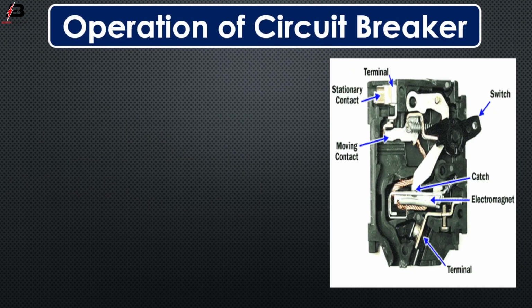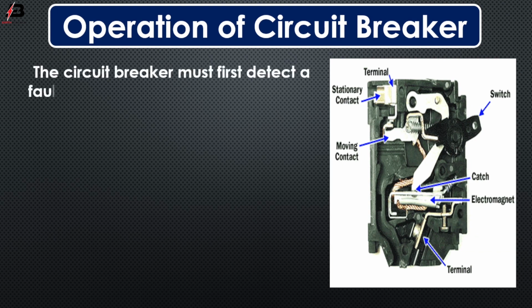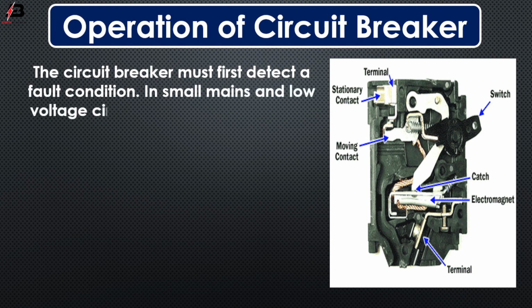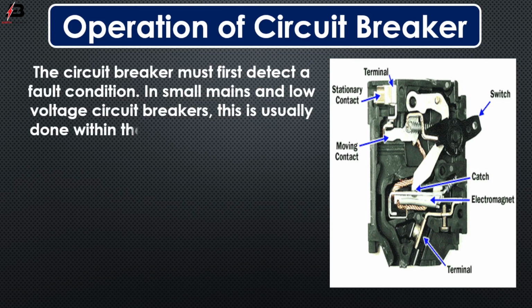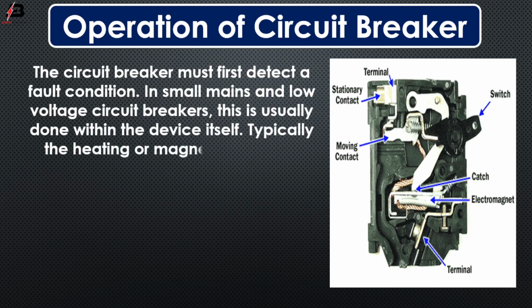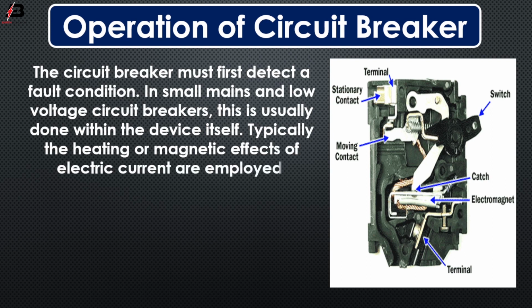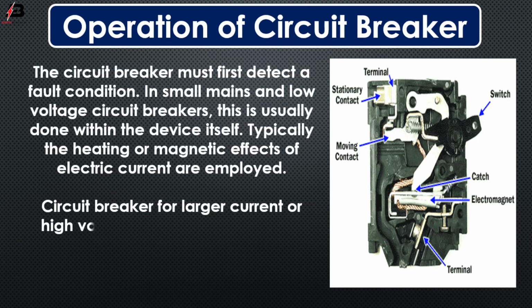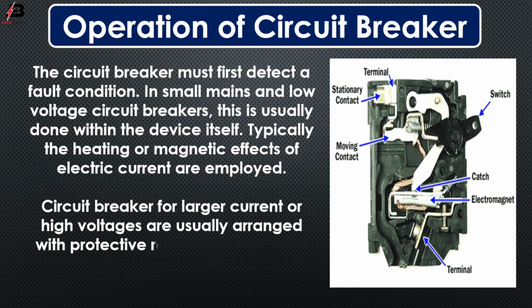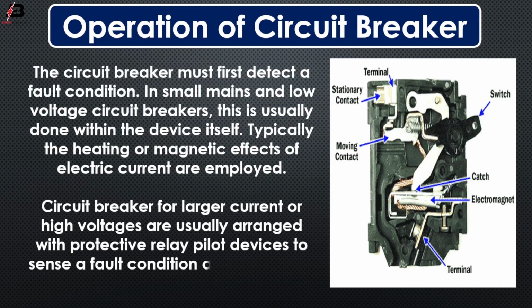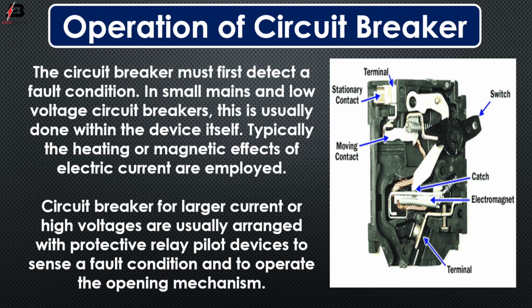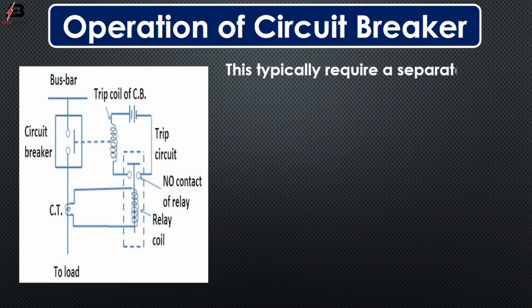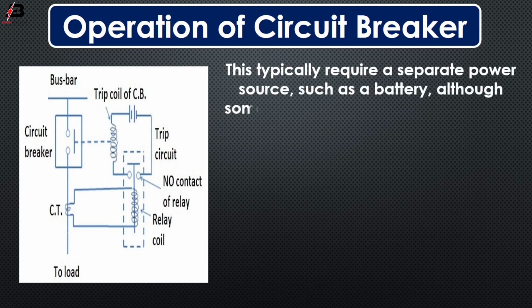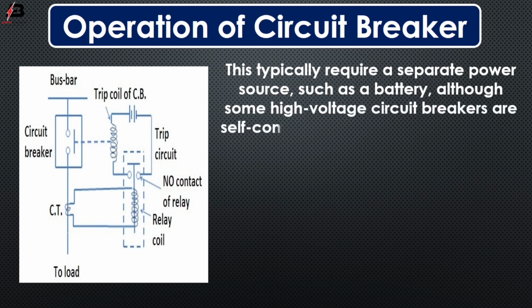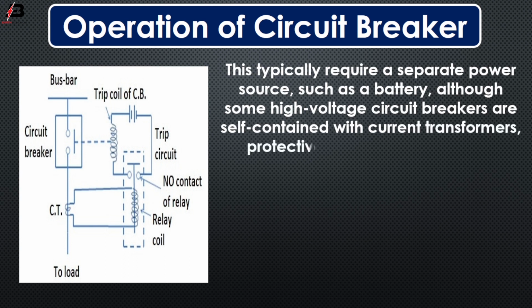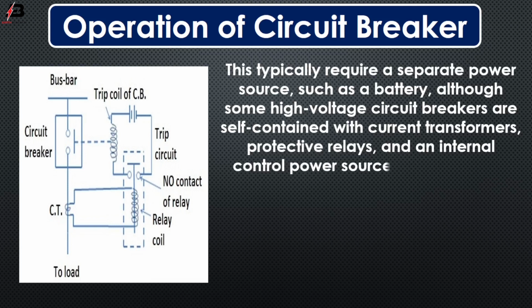Operation of circuit breaker. The circuit breaker must first detect a fault condition. In small mains and low voltage circuit breakers, this is usually done within the device itself. Typically, the heating or magnetic effects of electric current are employed. Circuit breakers for larger current or high voltage are usually arranged with a protective relay pilot device to sense a fault condition and to operate the opening mechanism. This typically requires a separate power source such as a battery, although some high voltage circuit breakers are self-contained with current transformers, protective relays and an internal control power source.